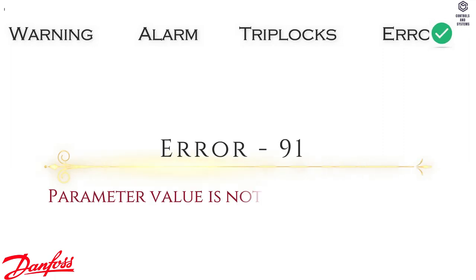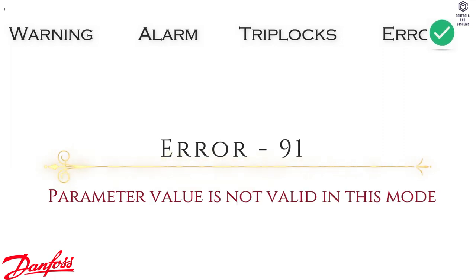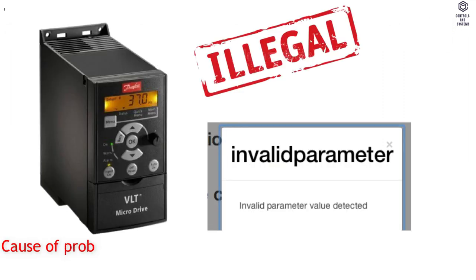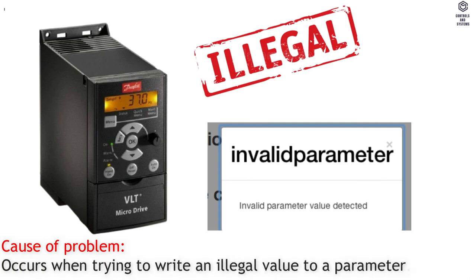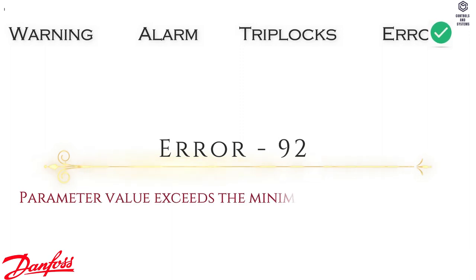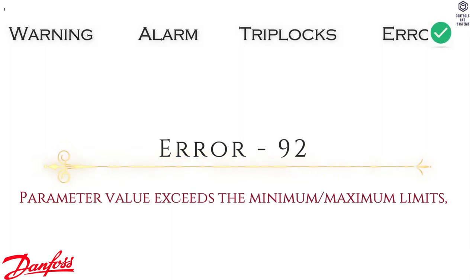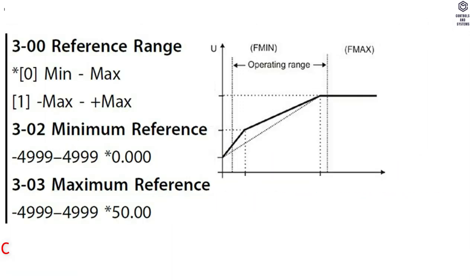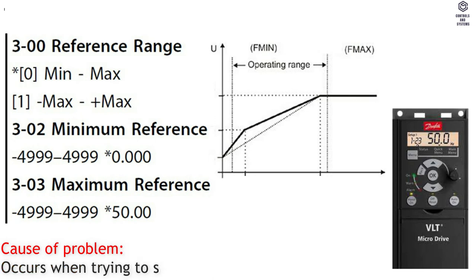Error 91: Parameter Value is Not Valid in this Mode. Cause of Problem — occurs when trying to write an illegal value to a parameter. Error 92: Parameter Value exceeds the Minimum/Maximum limits. Cause of Problem — occurs when trying to set a value outside the range.